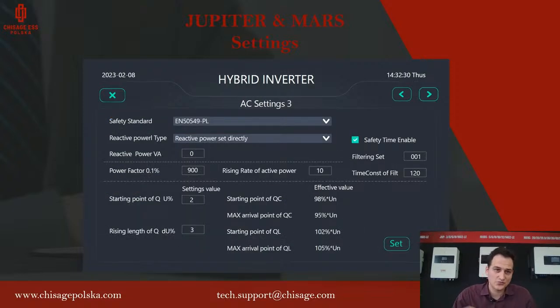Third page, we have to pick the safety standard according to the safety standard in our country. And we have the safety time enable box. That means the inverter will extend the time before it reconnects to the grid. So if we don't want the inverter to reconnect as fast as it can, we can extend this time and pick this safety time enable.